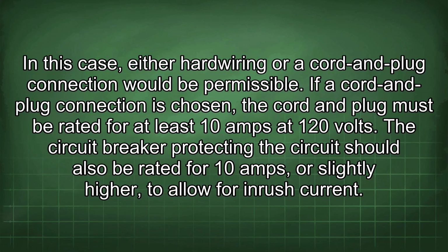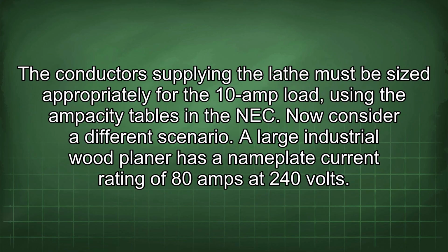If a cord and plug connection is chosen, the cord and plug must be rated for at least 10 amps at 120 volts. A circuit breaker protecting the circuit should also be rated for 10 amps, or slightly higher, to allow for inrush current. The conductors supplying the lathe must be sized appropriately for the 10 amp load, using the ampacity tables in the NEC.